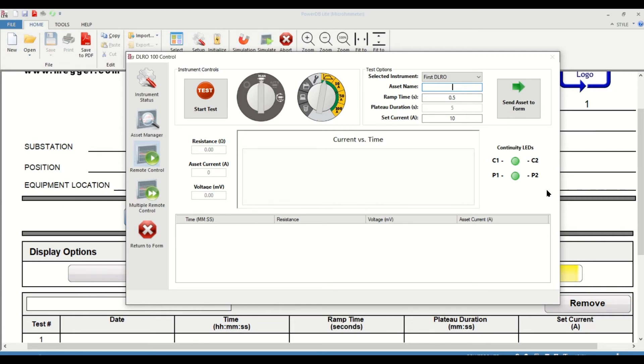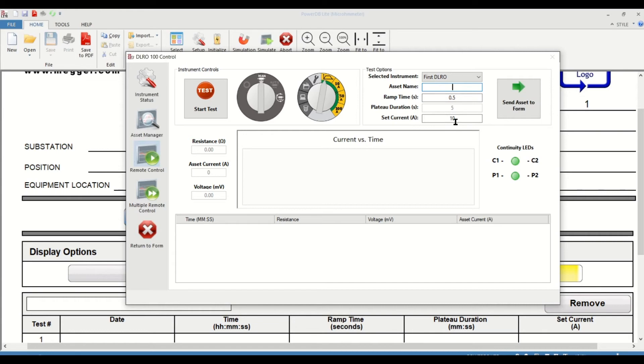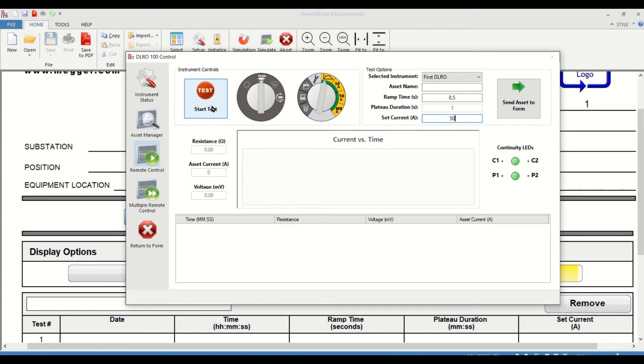I have a test specimen connected here. I'm going to make sure I have everything set up, such as the ramp time, plateau duration, and set current. I'm going to change the current to about 50 amps. You can just edit it using your keyboard. And once that is complete, I will be hitting the start button. You might hear some beeping sounds because of the remote operation, and that's normal.